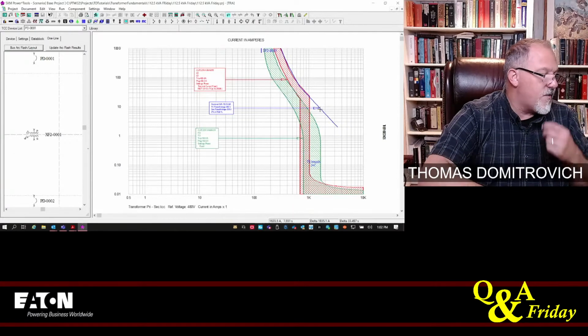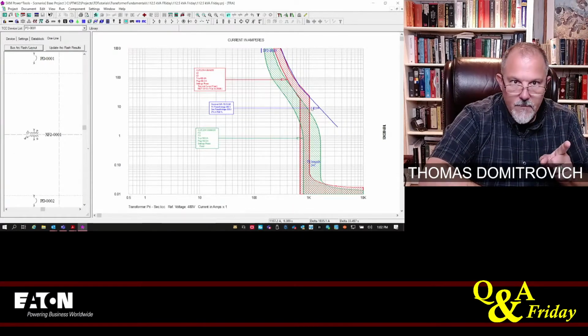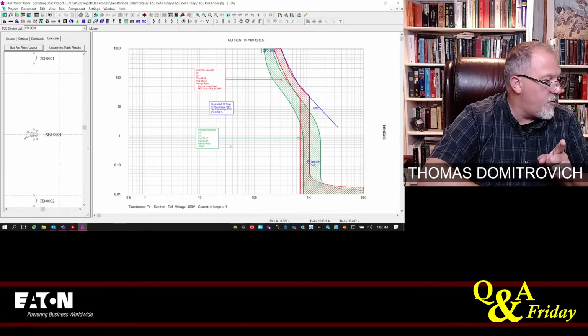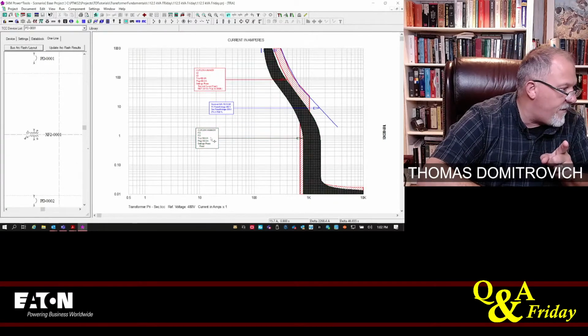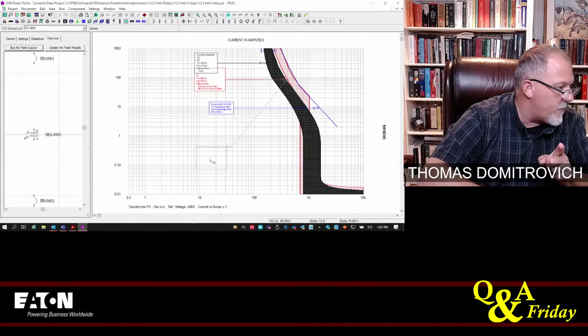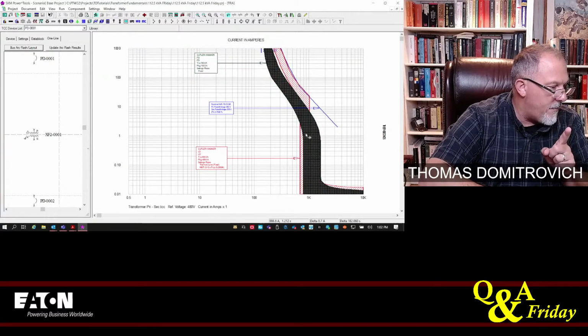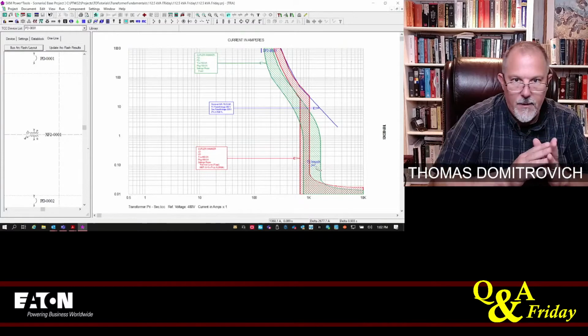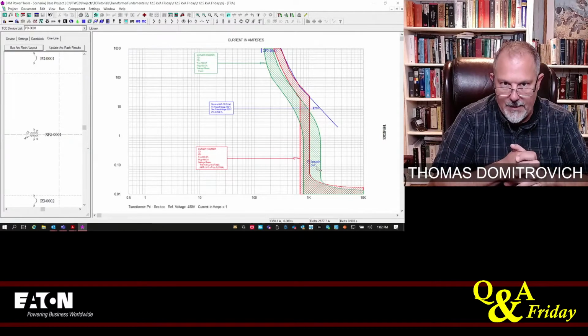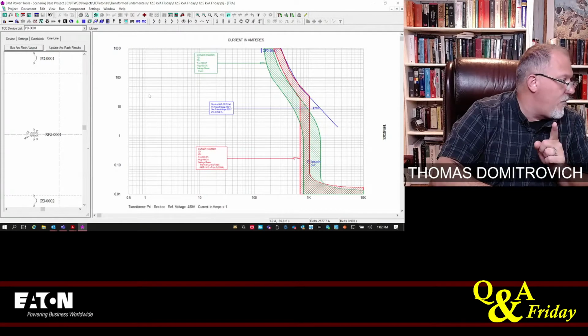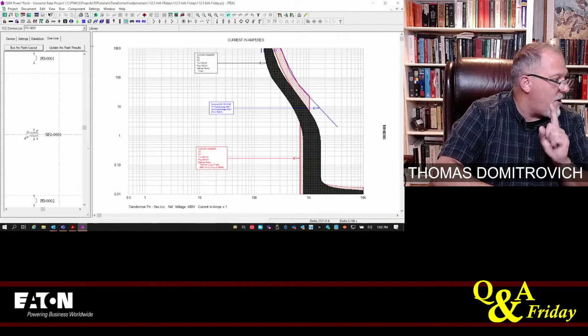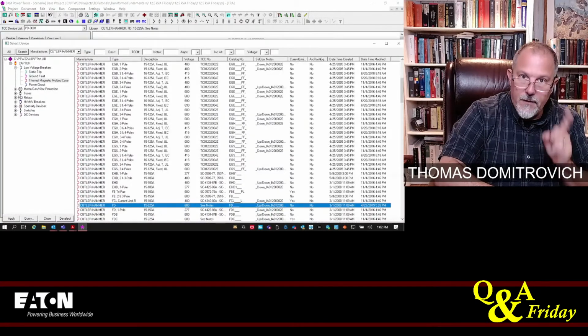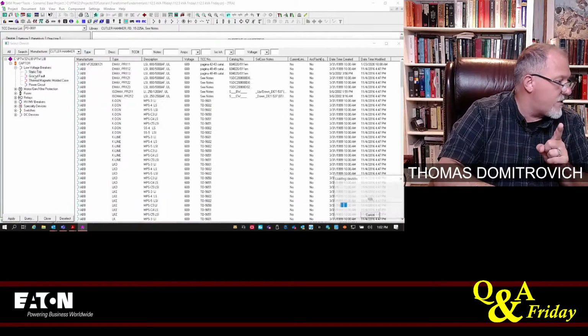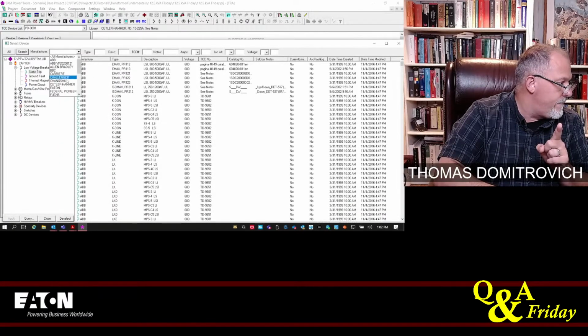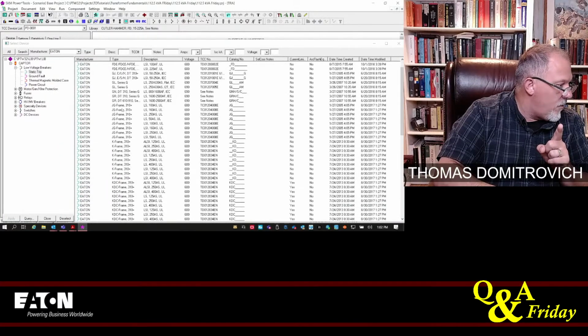All right, so my transformer damage is the blue line. Transformer damage, this green circuit breaker is the 150. So I'm going to move that up and the red one down. So that's my primary breaker, and you'll notice that it is clobbering my inrush current. So that's an FD 150. Let's do this. Before I get off of a 150, I am going to try to pick a different circuit breaker. Let's go to an electronic circuit breaker. And go to a 150.